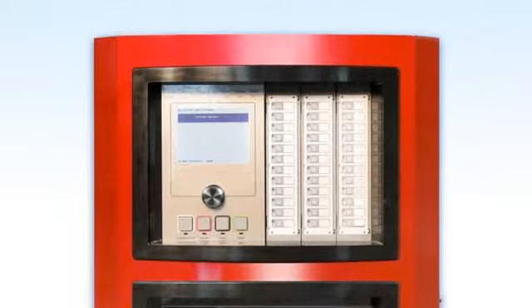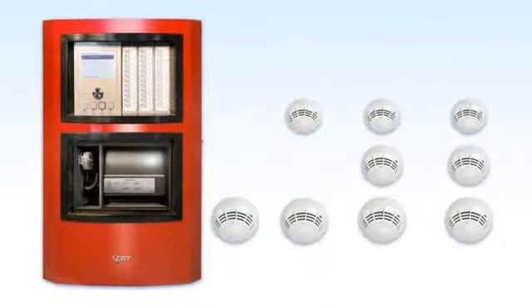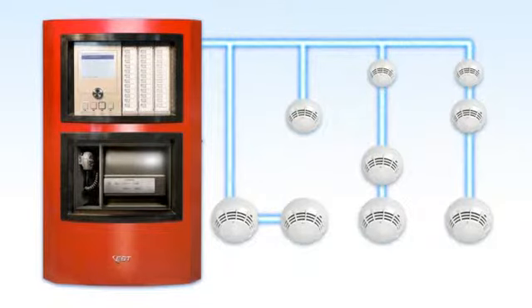The control system's user-friendly maintenance program shows the current state of each CO detector and other pertinent messages. Individual CO detectors may be turned off temporarily from the control panel or placed in maintenance mode for testing. When the CO sensor's electrochemical cell reaches its end of life — approximately six years — the detector signals a trouble condition to the control panel. The low-cost single sensor daughter board is field replaceable, resulting in the most cost-effective solution currently available in the industry.